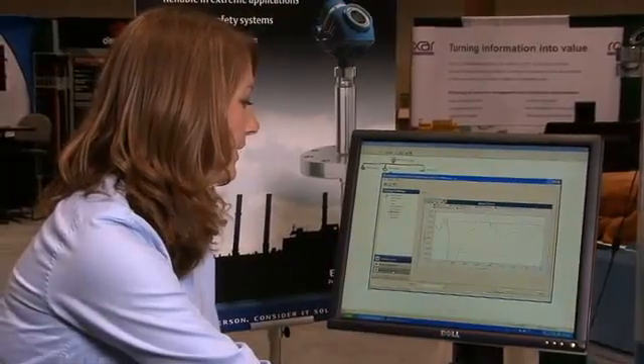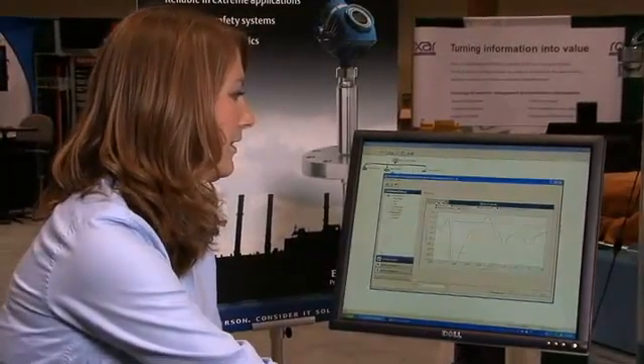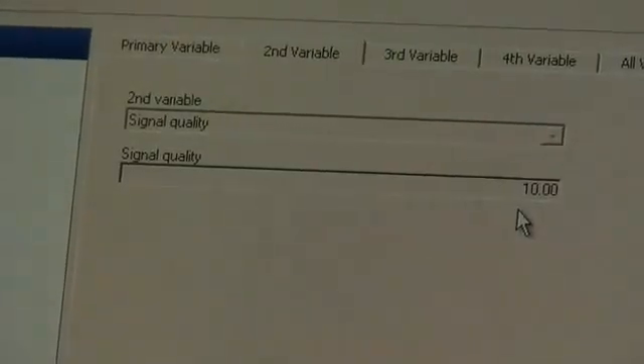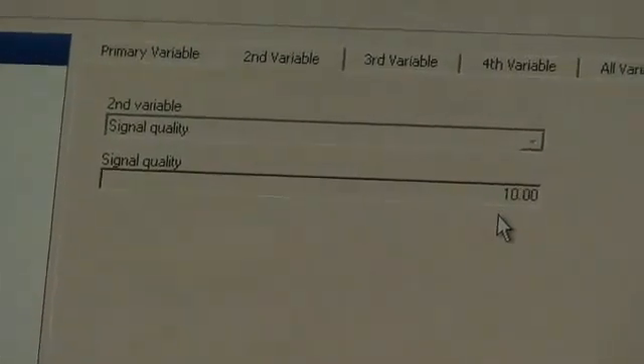Okay, now I'm going to go back to the signal quality and see what the value is. As you can see we have a signal quality of 10 representing a clean probe with no disturbances from contamination.